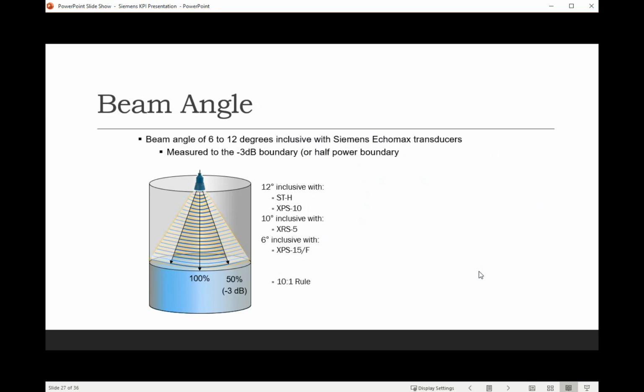Actually, beam angle is one of the most misunderstood pieces with regard to both ultrasonic transducers and radars. And really to dispel some of the myth or the mystery of that, if you go to the true definition of what a beam angle is, and this goes back to the days of radio communication, beam angle from an antenna or a source is defined as twice the angle at which the off-axis measurement is 3 dB less than, or half the power of, the center spot. So in English, really what that means is that your strongest signal is going to be right down the center line of your transmission axis.